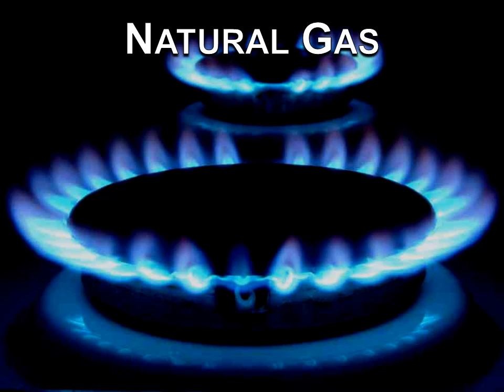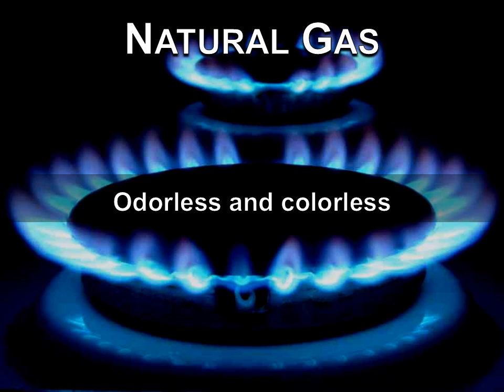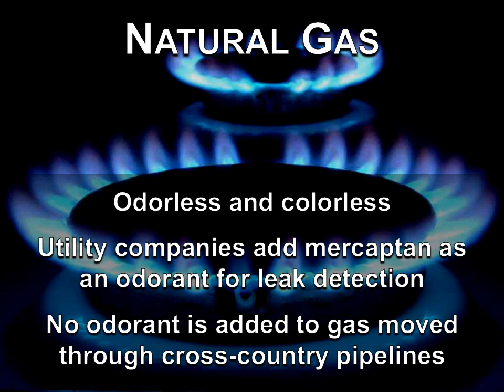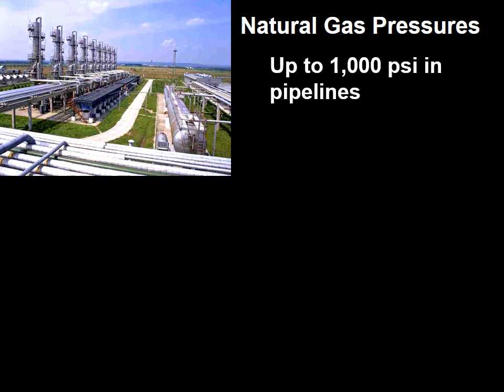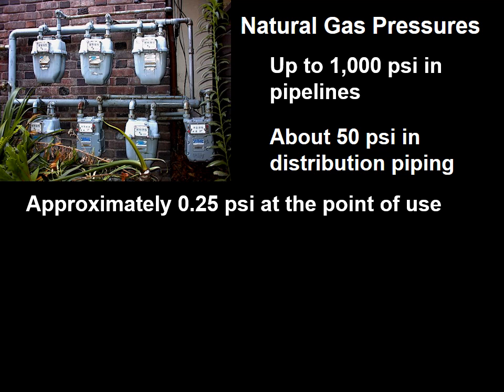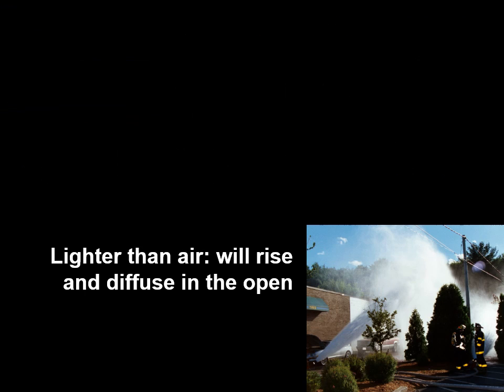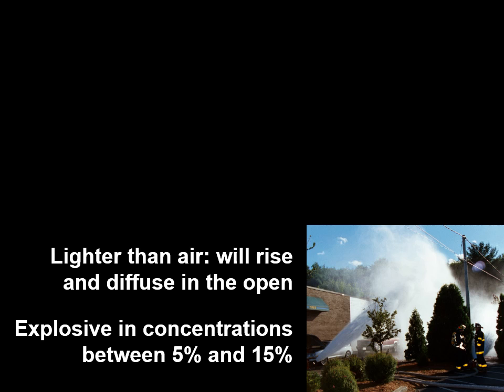Natural gas is comprised of mostly methane with ethane, propane, butane, and pentane gas added. It's odorless and colorless. Utility companies add mercaptan as an odorant for leak detection. That's the smell that we get when we smell gas. No odorant is added to gas moved through cross-country pipelines. Natural gas pressures can be up to 1,000 psi in pipelines and about 50 psi in distribution piping, approximately a quarter psi at the point of use. It's lighter than air and will rise and diffuse in the open. Explosive concentrations can be between 5 and 15%.